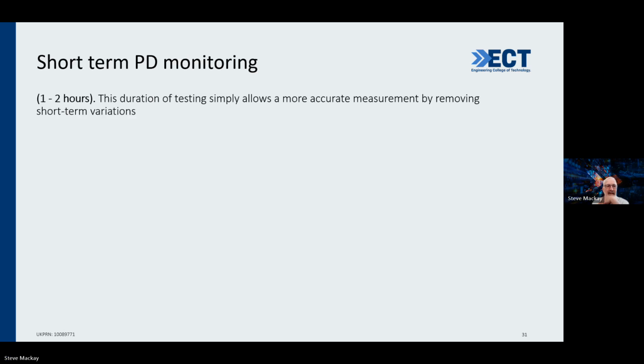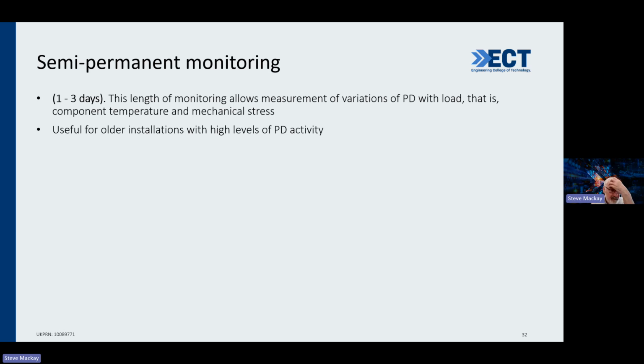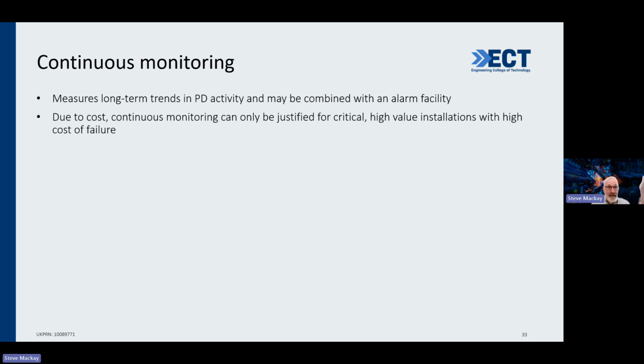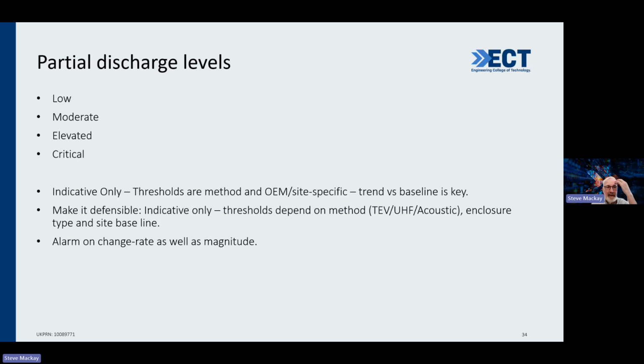So you can do short-term partial discharge monitoring, 1 to 2 hours, to avoid any short-term variations. But 1 to 2 hours just gives you that particular point and gets rid of any variations. Over 1 to 3 days gives you measurement of variations over component temperature and mechanical stress, and that's quite useful. And if you can do continuous monitoring of partial discharge, that is really useful because then you can automate the monitoring process. But you may find that will cost too much, so it may not be the way to go.